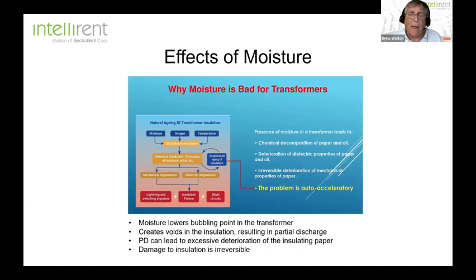And why is moisture bad? Well, what happens when you have moisture in your insulation is it lowers the bubbling point in the transformer. This bubbling creates voids in the insulation. It results in partial discharge, and that can lead to excessive deterioration of the insulating paper. And once you damage that paper, that damage is irreversible.